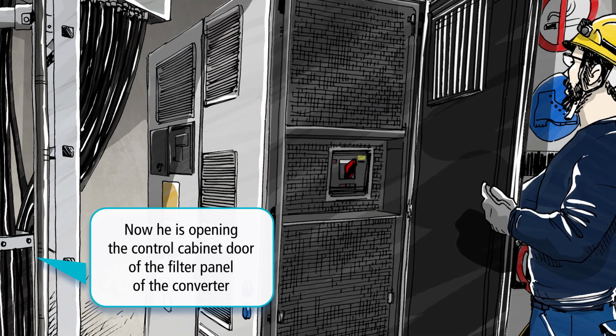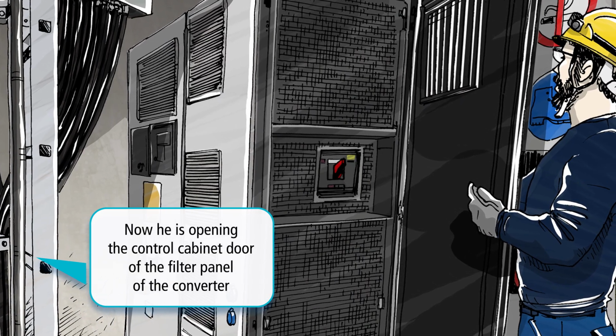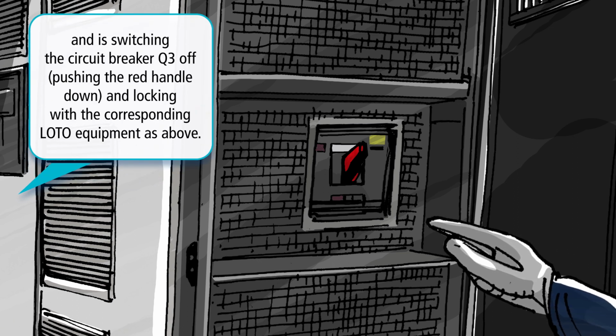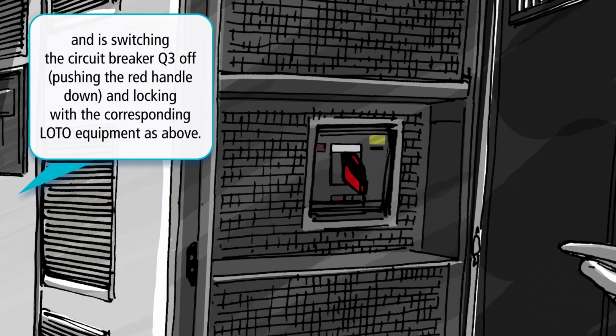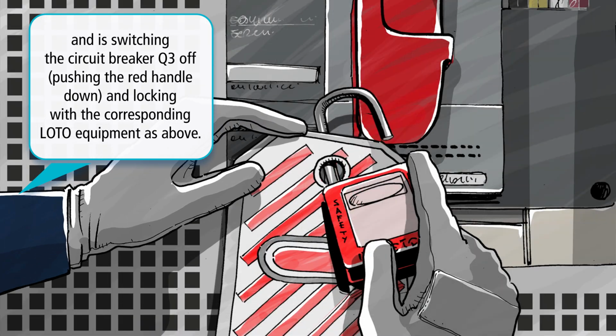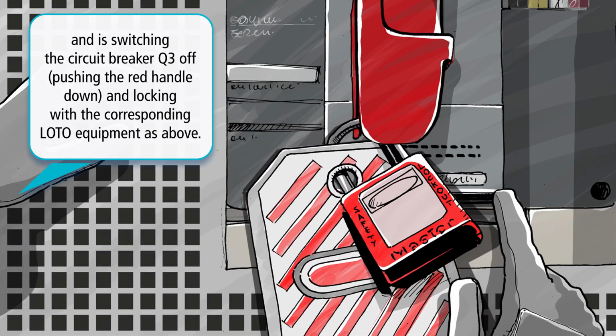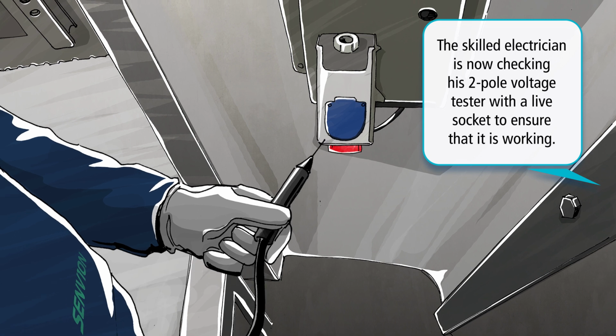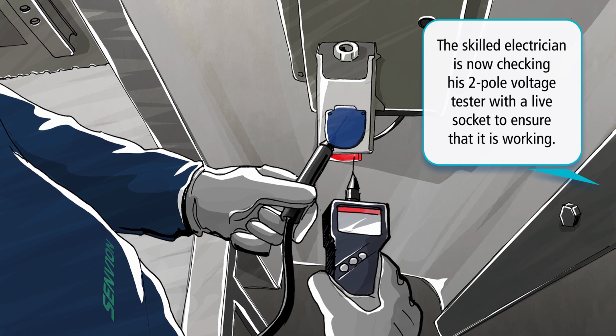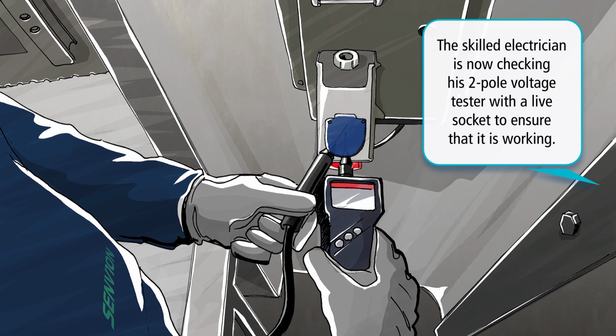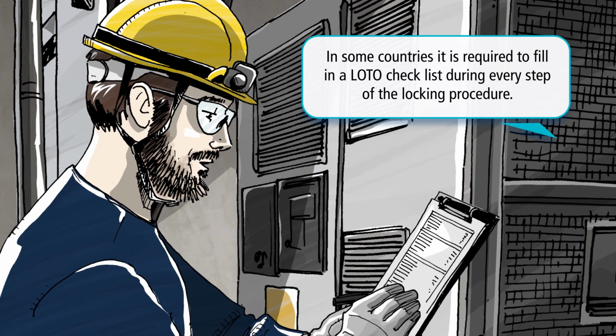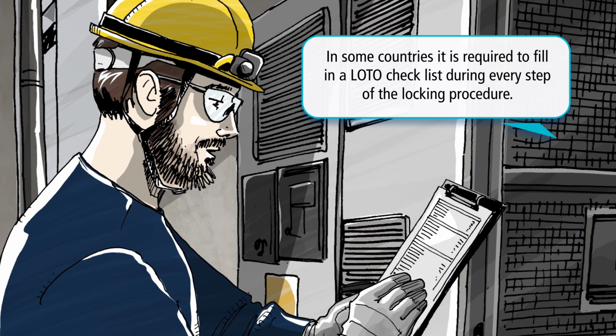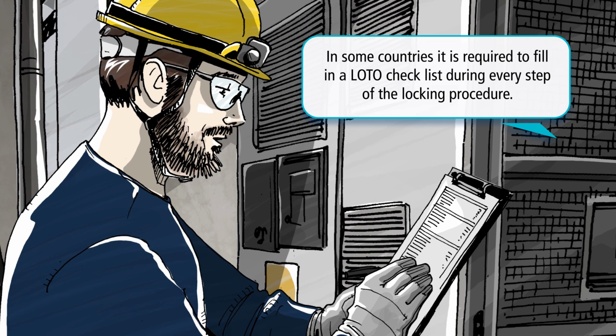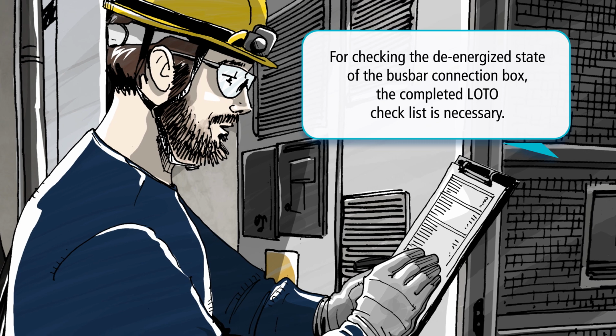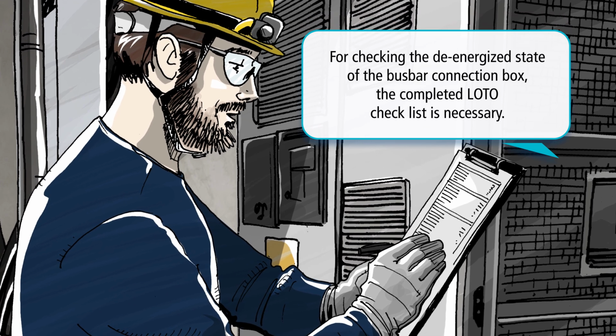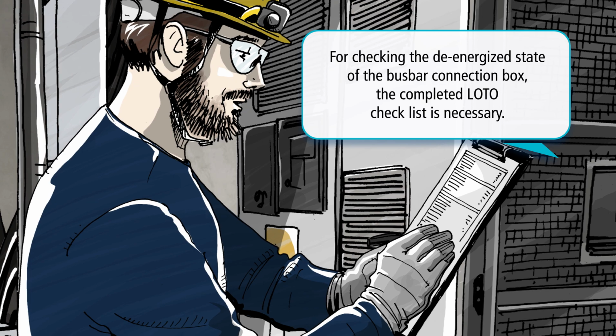Now he is opening the control cabinet door of the filter panel of the converter and is switching the circuit breaker Q3 off, pushing the red handle down, and locking with the corresponding LOTO equipment as above. The skilled electrician is now checking his 2-pole voltage tester with a live socket to ensure that it is working. In some countries, it is required to fill in a LOTO checklist during every step of the locking procedure. For checking the de-energized state of the bus bar connection box, the completed LOTO checklist is necessary.